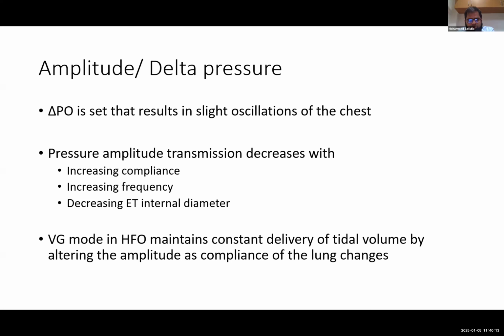It is the same mechanism as the VG mode in conventional ventilation. Once the baby's compliance improves and the baby requires lesser pressures, the delivered pressures, the PIP, will automatically decrease. Thereby delta P will decrease in conventional ventilation, and the delivered tidal volume will be constant. Similarly, in high frequency ventilation, once compliance improves, if you are not decreasing the amplitude, it will lead to more delta P transmission to the alveoli, more tidal volume delivery, which leads to hypocarbia. So just to avoid that, even HFO has a VG mode.